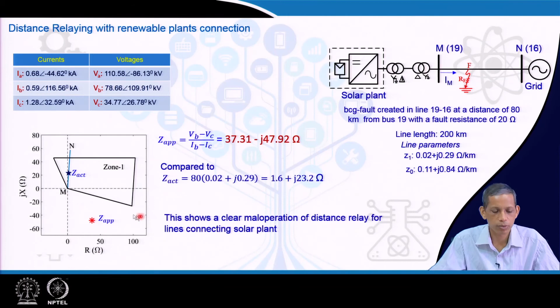Consider a solar plant connected to that same system. First, for clarity, consider a 3 phase fault. For a 3 phase fault, Z apparent equals VA upon IA, or VB upon IB, or VC upon IC, or V1 upon I1. So here we are talking about V1 upon IM. That equals the distance of fault x times Z1MN, the positive sequence line impedance, plus the modulating factor I1F upon I1M times RF. This is the corresponding voltage at this point, Vf, that modulates.